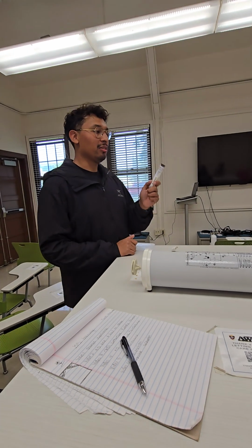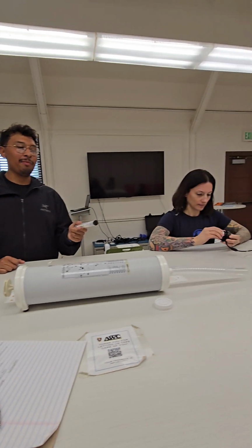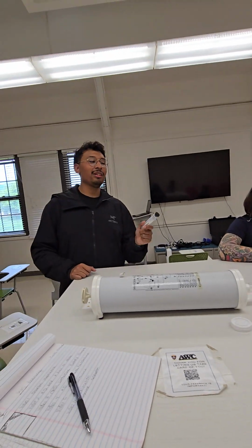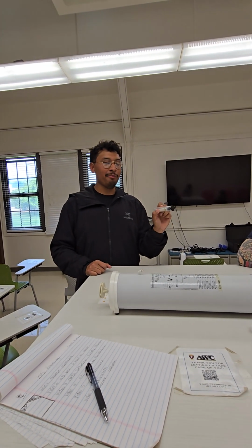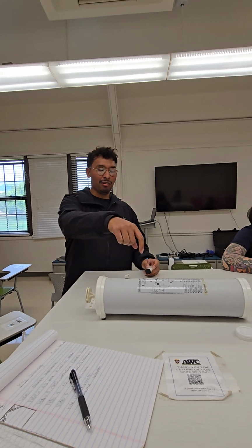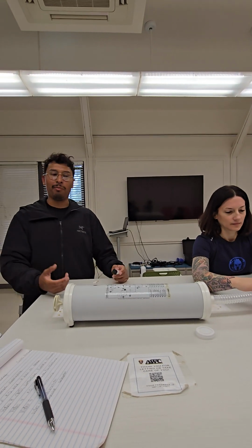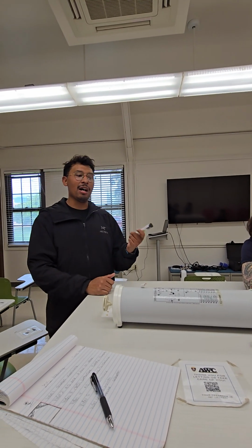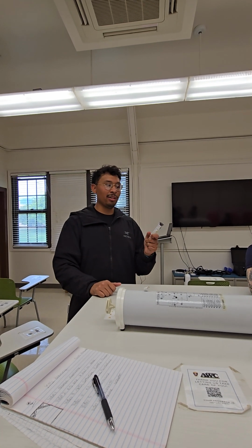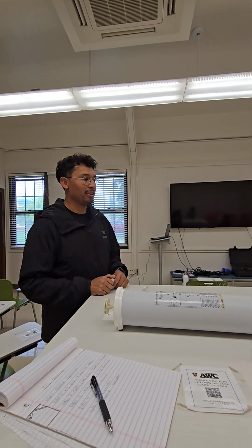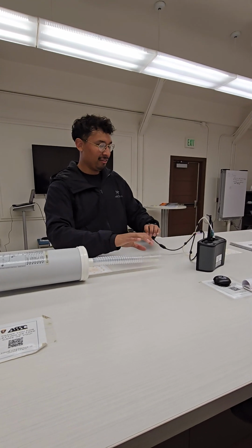Yeah, so you'll want to use the wind cap anytime you're testing outdoors. And if you're going to use the wind cap, make sure you calibrate the flow meter with the wind cap on it. You don't have to use it indoors unless you're going to have a fan in the room. And let me take this off.